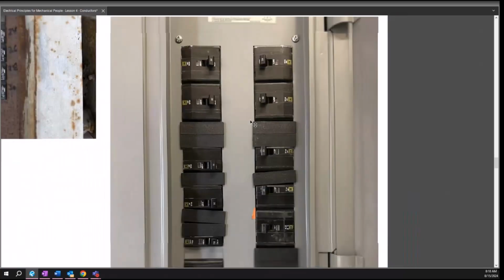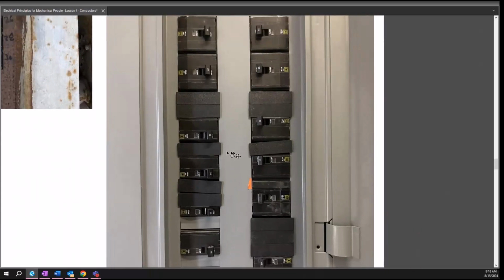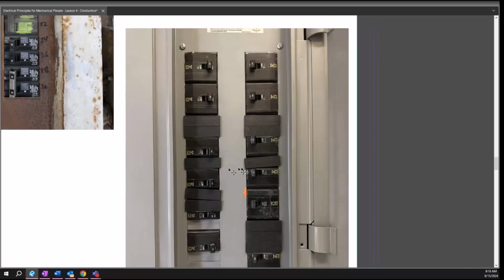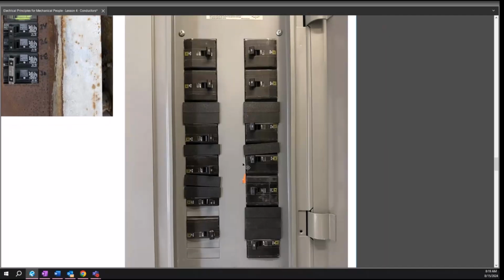It's not as clear here, but they just kind of randomly skipped side by side. Most people are like, 'why didn't they just push this 2-pole up?' Well, they could have — technically, electrically it would have worked totally fine. But they were trying to show, hey, this is a 240 high leg. You can actually see somebody put a piece of orange tape right there indicating that's the high leg phase. A lot of electricians will do installs like this to help others identify that this is not a 240 panel, not a 208 panel — this is 240 high leg. Does that make sense? Yeah.